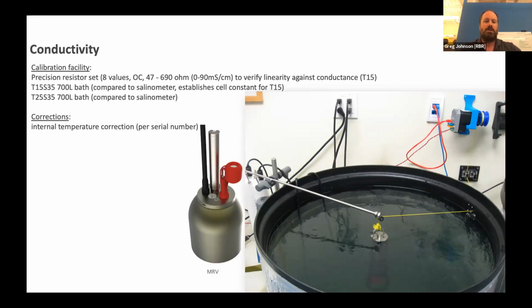The way we calibrate conductivity is we start off doing everything in air. We take a resistor set, 8 values ranging from a completely open circuit and then about 47 ohms up to 700 ohms. And that equates to roughly a conductivity of 0 to 90 millisiemens per centimeter. And we're verifying linearity. The reason we're verifying linearity is because it should be there by design, but if the cell or the electronics are not linear, the rest of the calibration is a waste of time. And so we can do that in air at about 15 degrees Celsius. We then take a single measurement in our 15 degree 35 PSU bath, and that allows us to establish the cell constant, which converts between conductance and conductivity.